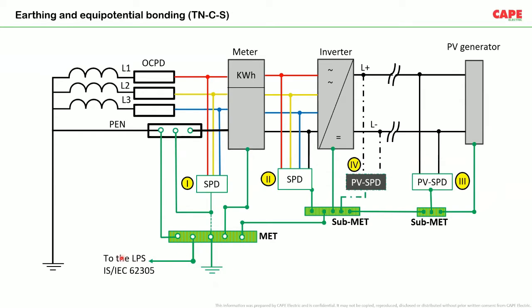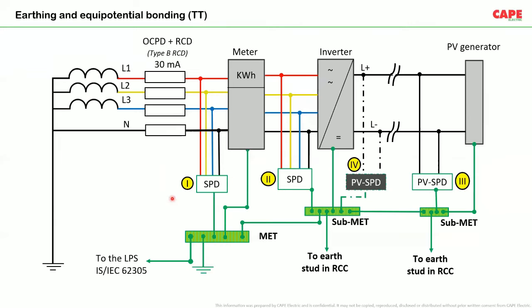The MET is also connected to the lightning protection system, also to the extraneous conductive part, which we always discuss in our seminars. Now, see, for example, this particular network is applicable for a TNCS network. Most of the standards, even including the Indian standards, show this picture, because the standards and regulations are made thinking that TNCS is followed by the utility. But in practice, TNCS is not followed by the utility company. As a result, we have to make a small change here.